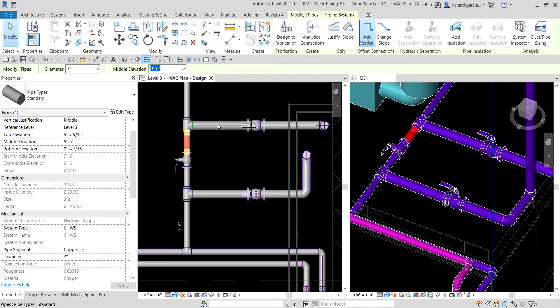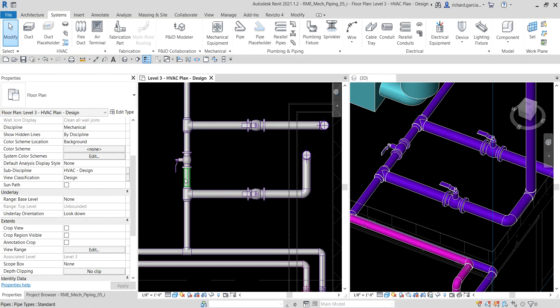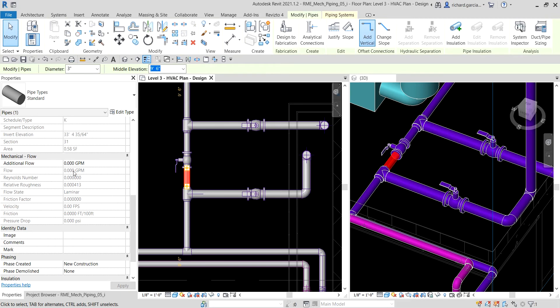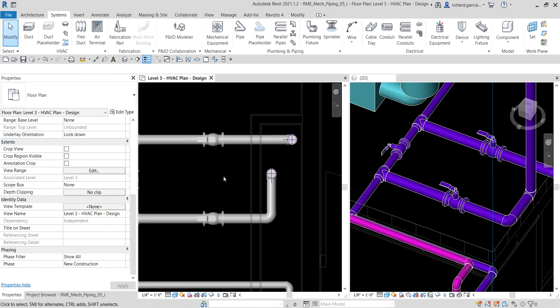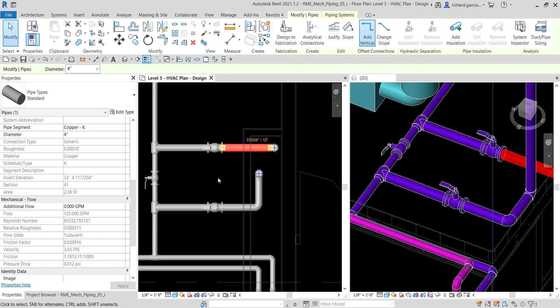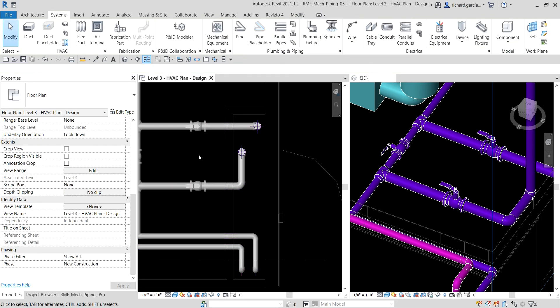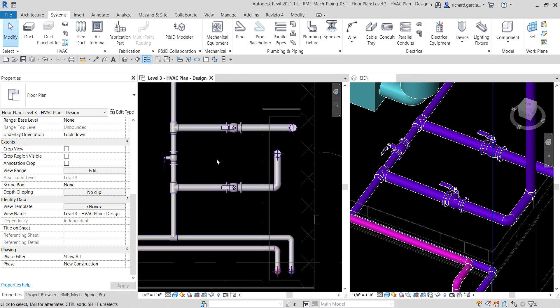If I select this pipe here, the flow there is zero. And this pipe that I have here, the flow is also zero. Now on the top horizontal pipe — the flow from the cooling tower — this is 125 GPM. And it's the same for the bottom horizontal pipe, which is the flow from the cooling tower — also 125 GPM. So currently the system is designed to run in cooling mode. You add valves to the cooling tower to enable the system to alternately run in heating mode.